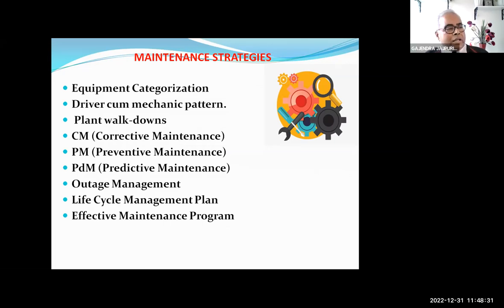I would like to share one small incident, or my experience, or what I have seen. I was at a nuclear power station during the commissioning stage, and the unit auxiliary transformer was a 35 MVA, very big transformer. We used to carry out dissolved gas analysis. Dissolved gas analysis is something electrical engineers should understand. It gives the various gases inside the transformer oil, and it will give the condition, whether a high temperature condition or a fault is there.